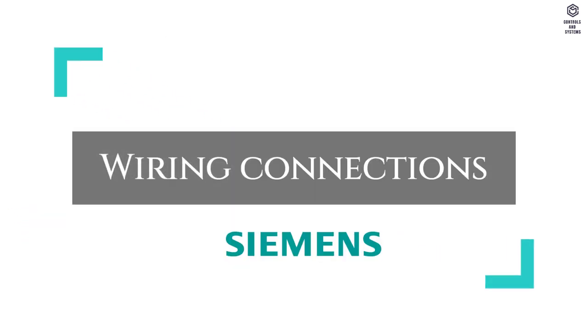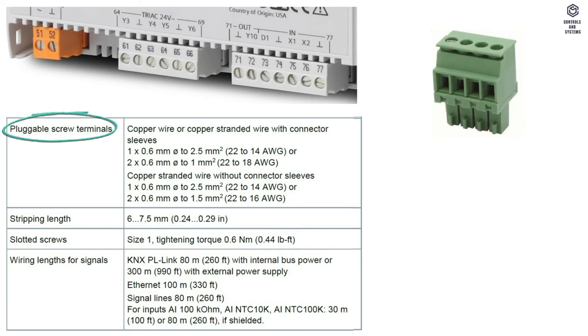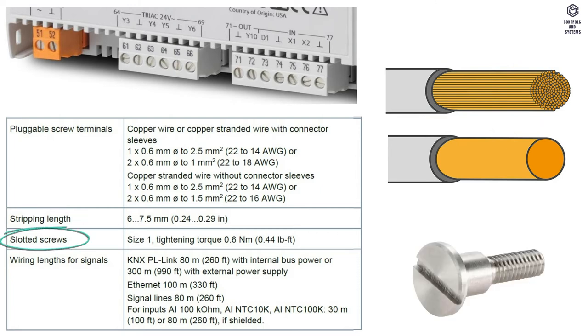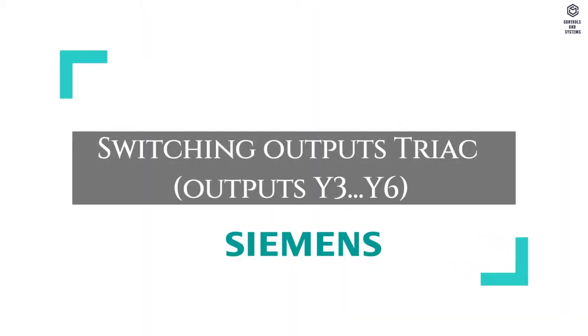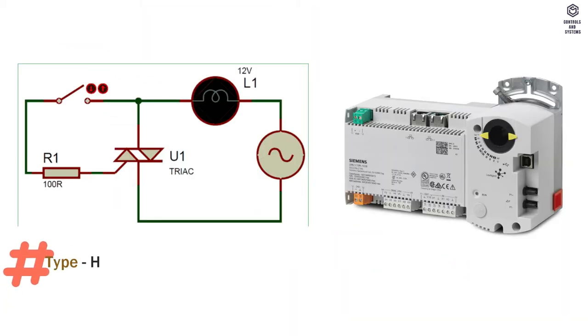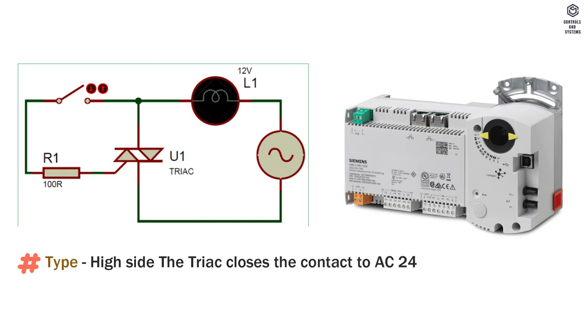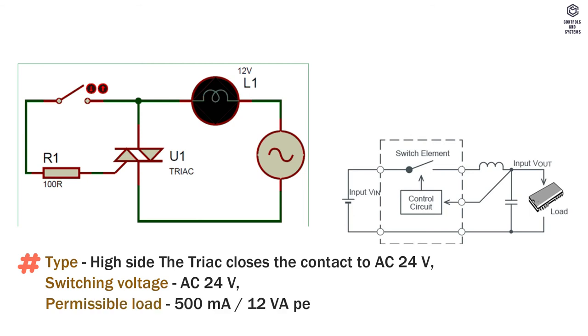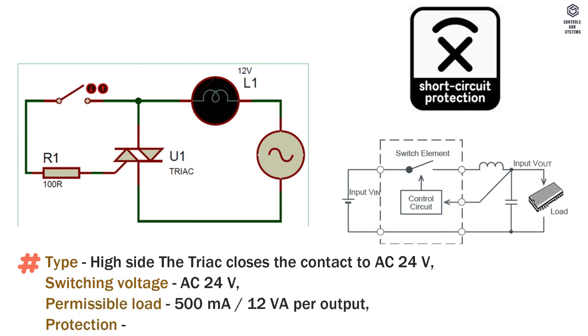Wiring connections: pluggable screw terminals use copper stranded wire without connector sleeves. Stripping length, slotted screws, and wiring lengths for signals are shown in the table. Switching outputs TRIAC: type is high side, and the TRIAC closes the contact to AC 24V. Switching voltage is AC 24V. Permissible load is 500 mA or 12 VA per output. Protection is short-circuit proof.